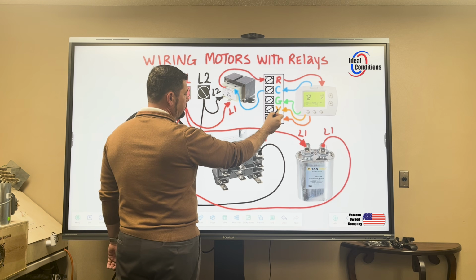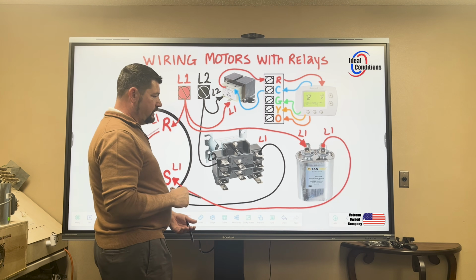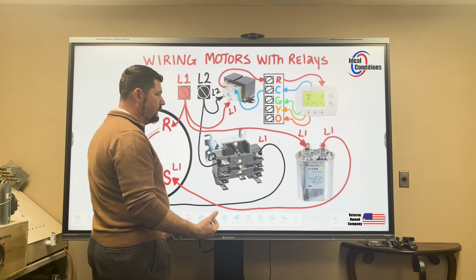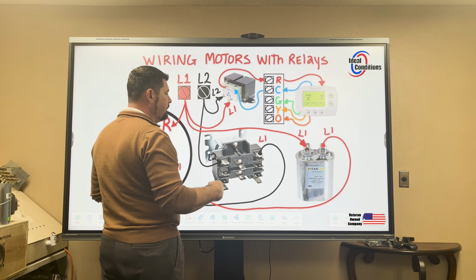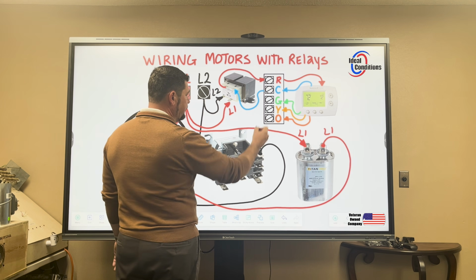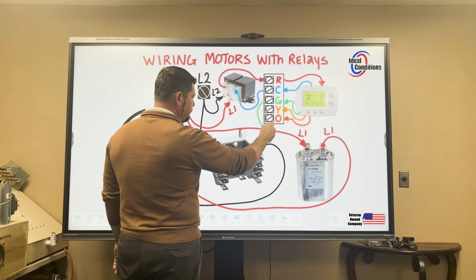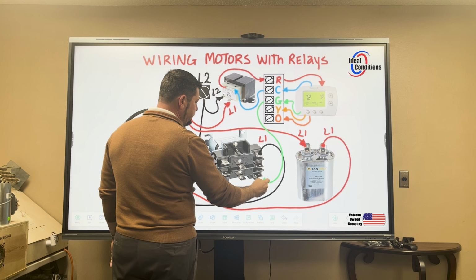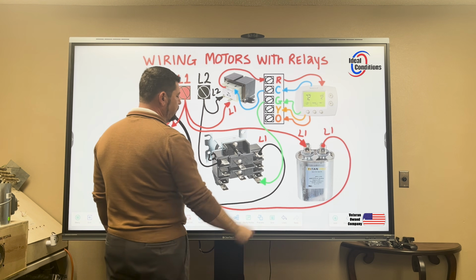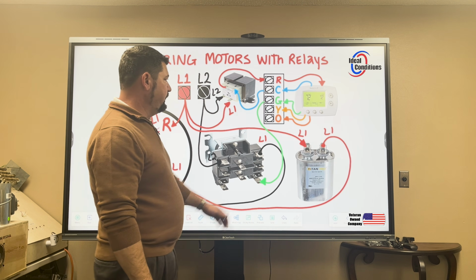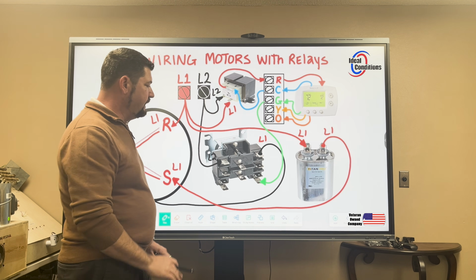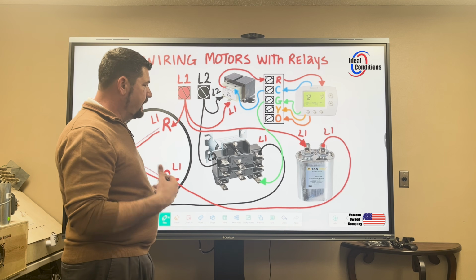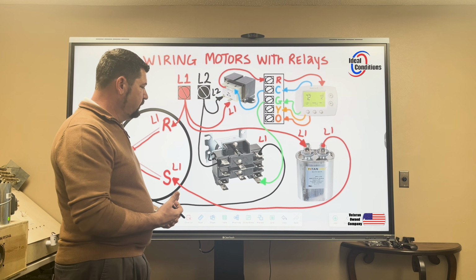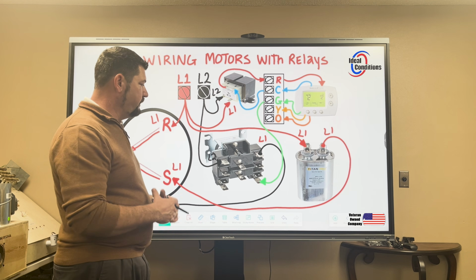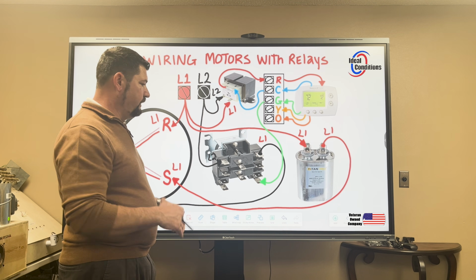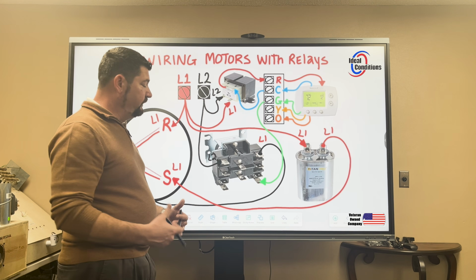The fan's always going to run with the contactor, whether it's contactor only or contactor with reversing valve, right? If we had a W terminal and it was energized, the fan's always going to run with it. So we really want to hook our relay up to this terminal here, which is the G. G is not for ground, not in the air conditioning world. In the electrical world, yes, but not in HVAC. Everything is color coded for the next guy coming out there. That next individual needs to be able to recognize the patterns that are unique in our industry and that are very redundant. This way we can get through every call, every job very safely and efficiently.